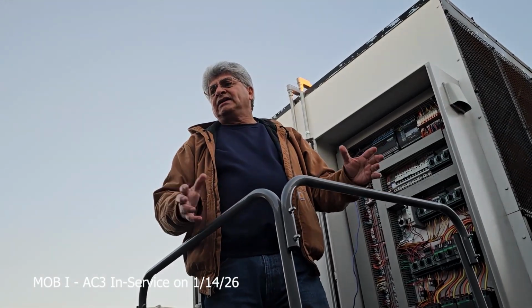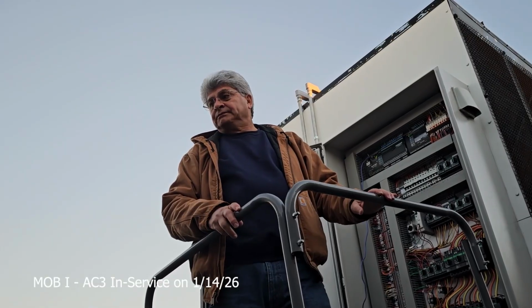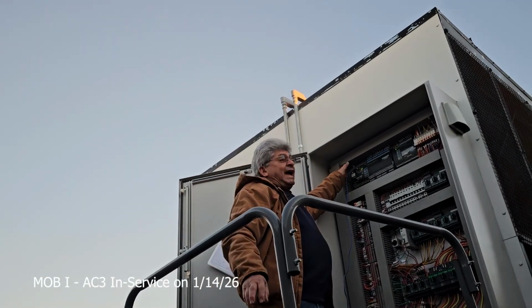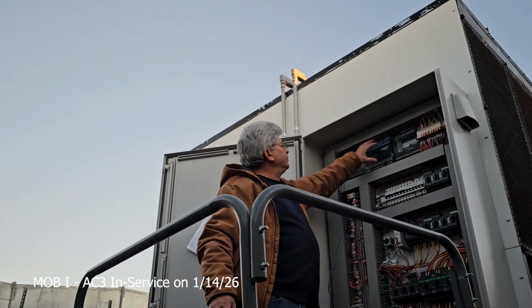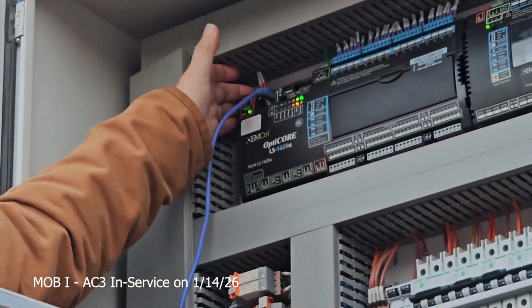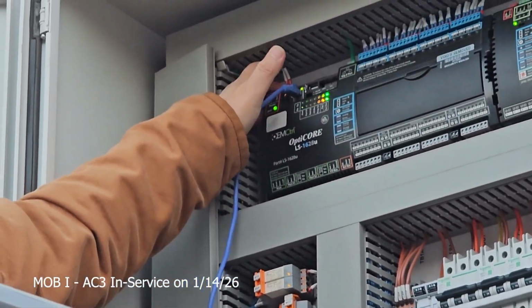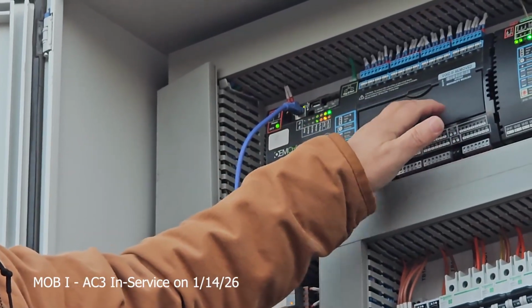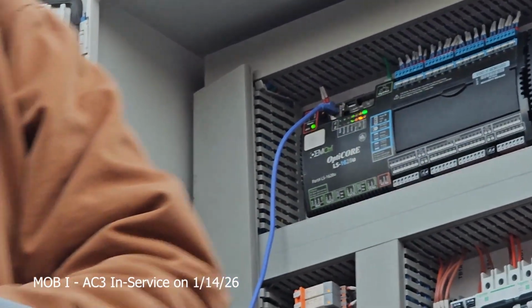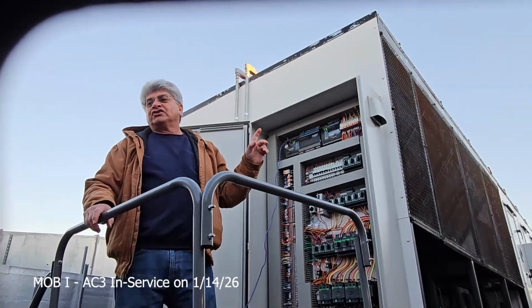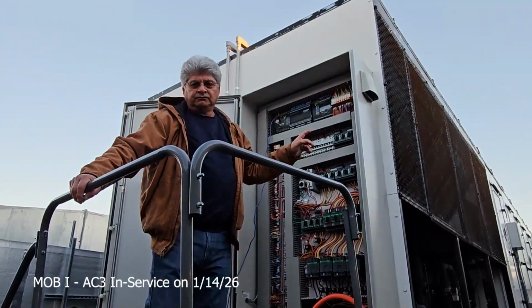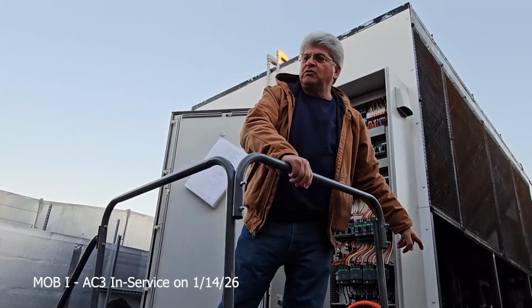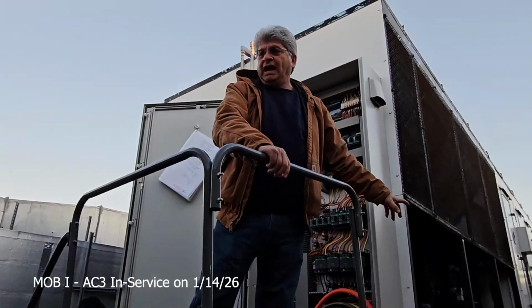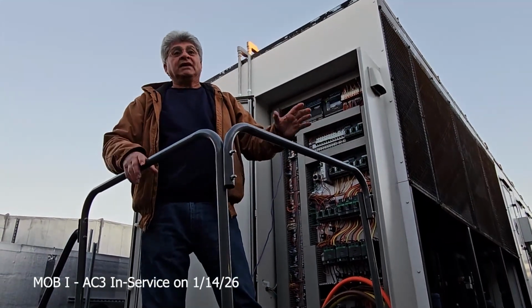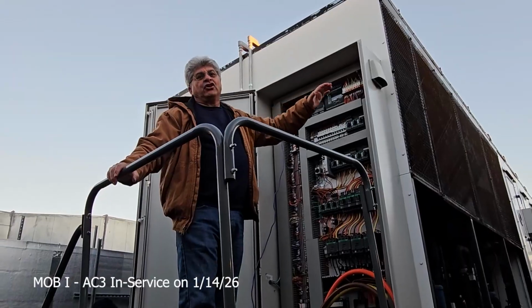I don't know if you guys get that a lot here. So soft reset is like the top where you reset at the top, right? Yep. There is no high voltage up here, so I can put my hands on everything. So you don't have to be afraid. Once you reset that switch up here, that will reset this controller. On a soft reset, she'll turn on your cooling within 5 minutes, and your fans already should be running. This doesn't control your fans. They're controlled elsewhere.